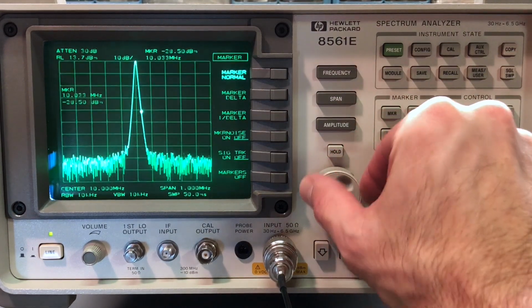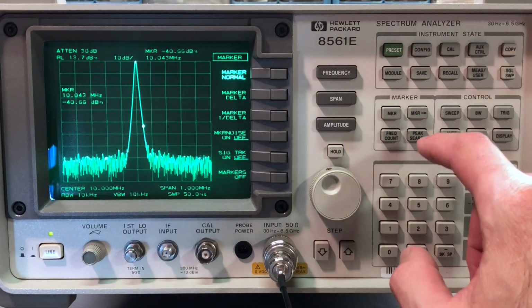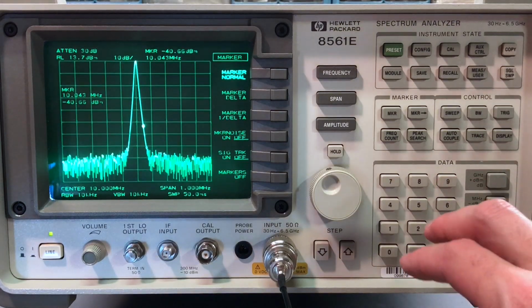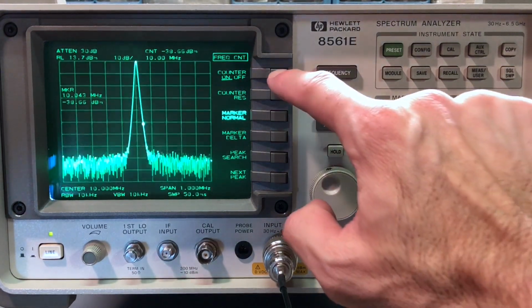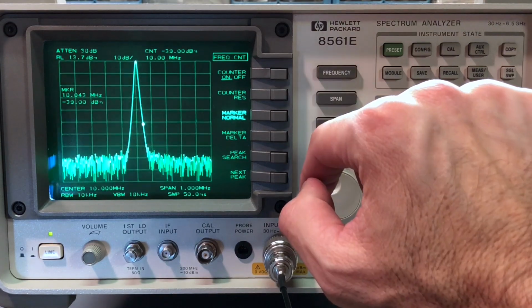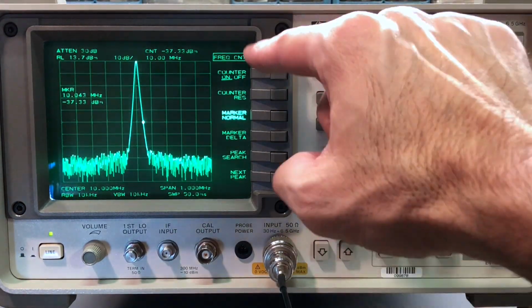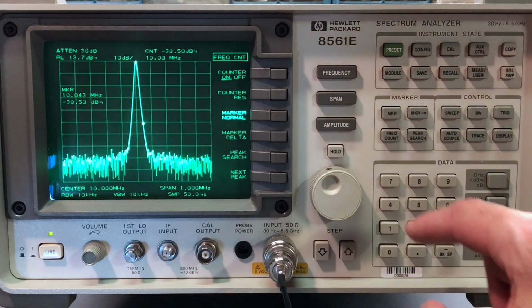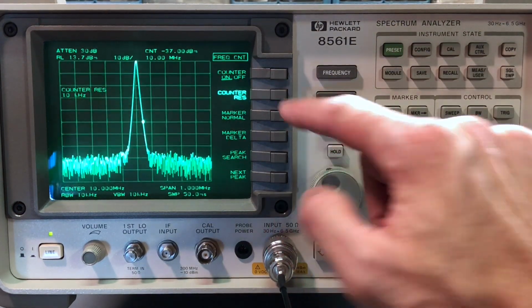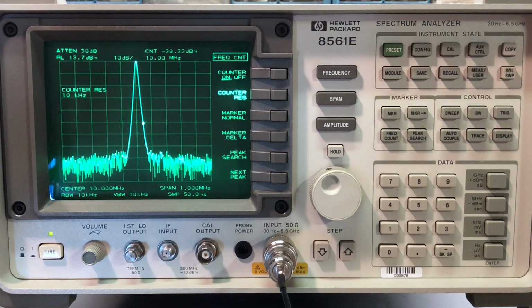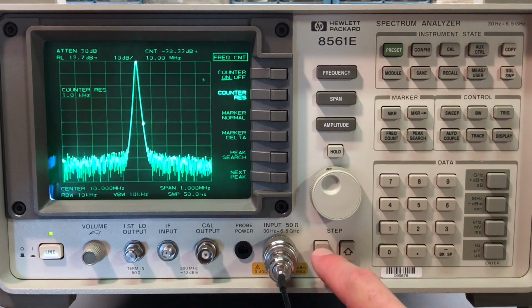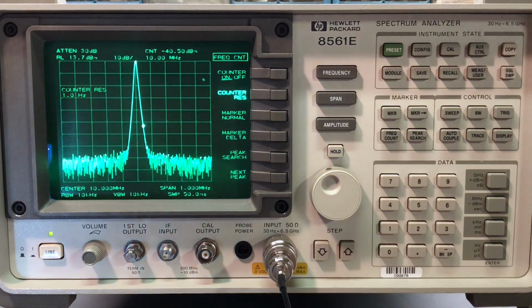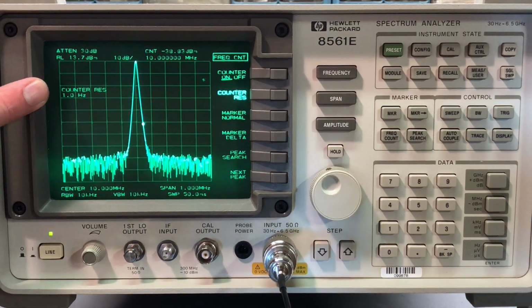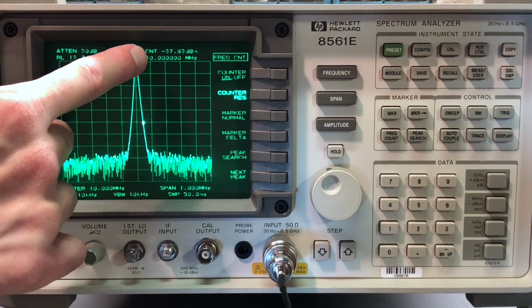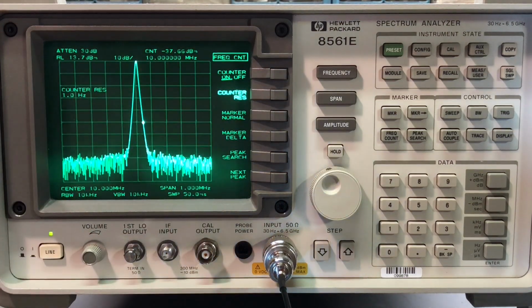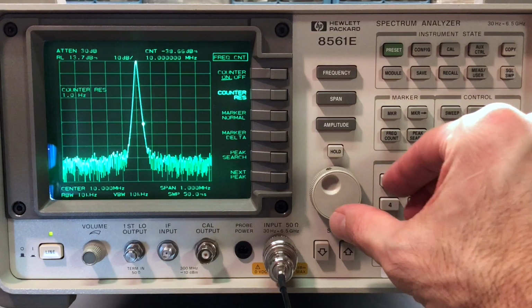So let's take a look at the frequency counter function. If I put marker and I just move the marker off of this peak a little bit, if I come over here to the frequency counter right here, turn the counter on. I think it was on already when I hit the button. Anyway, frequency counter is now turned on. Let's move the counter resolution. So the counter resolution is now 1 hertz, okay? And we can see up here the counter right there, 10 followed by all zeros, very, very accurate. So it's reading exactly what is expected.